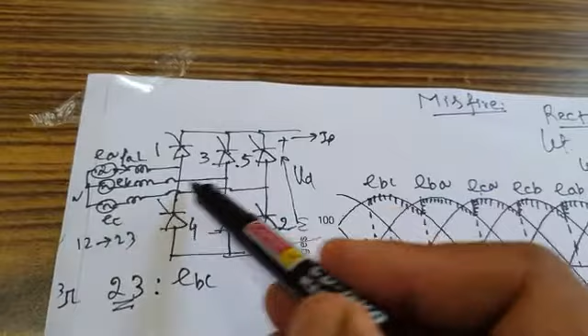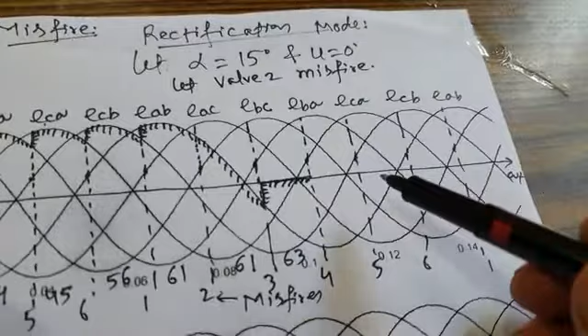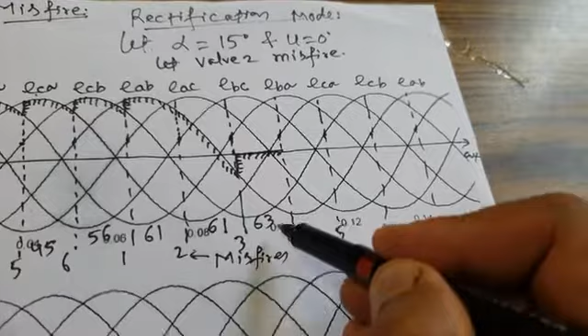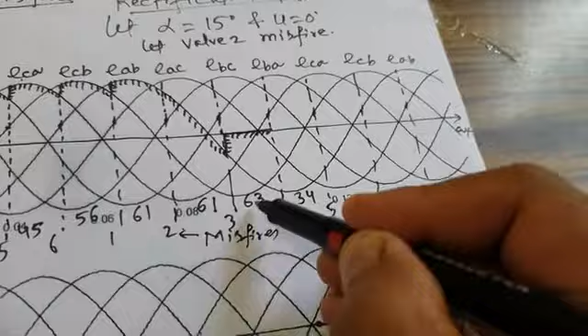When 6 is conducting, it is connected to EB. So its anode voltage is EB and cathode voltage is EA. So its commutation voltage is EBA. And you can see EBA is positive. Since the commutation voltage of valve 4 is positive, it will immediately go into conduction, and conduction will change from 3-6 to 3-4. Now 4 is the incoming valve, 6 is the outgoing valve. As soon as 4 is fired, 6 goes out. So conduction will change from 3-6 to 3-4.